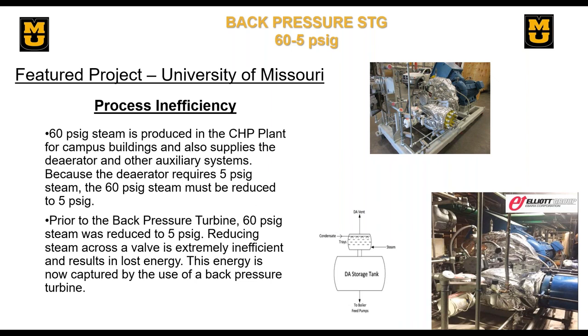So to give you a real life example of one of these pressure reducing type stations, the University of Missouri was a project that we did a few years ago. They identified some process inefficiencies where their central combined heat and power plant was producing 60-pound steam, distributing it to the campus, and also using it for other things, such as their deaerator. They identified a process inefficiency there, where you're reducing the pressure from 60 down to 5 for that deaerator. There's a significant amount of steam flow. Why not try to capture some of that energy in a steam turbine?